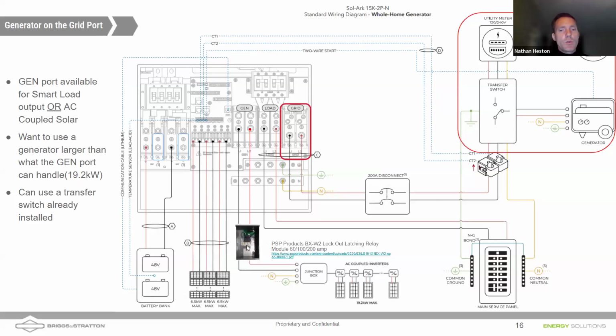The other thing you can do is use one of these PSP products. So if you aren't using a Briggs & Stratton transfer switch, you can install one of these PSP products. These are lockout latching relays, and they're programmable. They come in 60 amp, 100 amp, 200 amp versions. Likely you're just going to need a 60 amp version, because most systems that have AC coupled solar are 40 amps or under, just based on the common 120% rule for a 200 amp service would be 40 amps of AC coupled solar. So some examples.